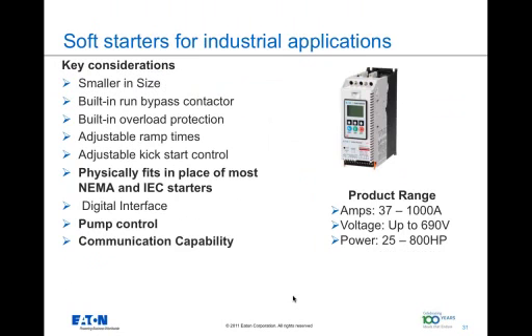An industrial user typically looks for the following in the soft starter. They're looking for a soft starter which is smaller in size, compact, but it has all the high-end feature set, including the bypass contactor, overload protection, adjustable ramp times, adjustable kickstart control, advanced monitoring and protection capability, communication capability, and such. And Eaton does provide soft starters for these industrial applications, and our product goes up to 1,000 amps, up to 690 volts, and about 850 horsepower or so.